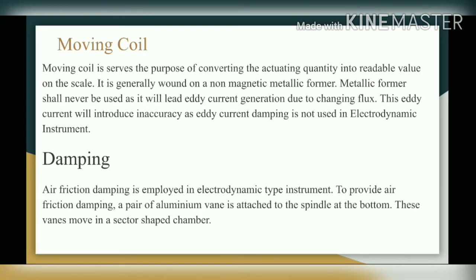Next is damping. Air friction damping is employed in the electrodynamic type instrument. To provide air friction damping, a pair of aluminium vanes is attached to the spindle at the bottom, and these vanes move in a sector-shaped chamber. So for damping purpose, air friction damping method is used.